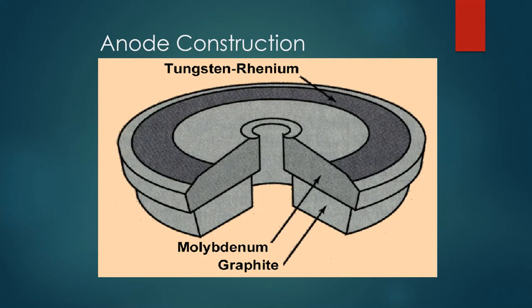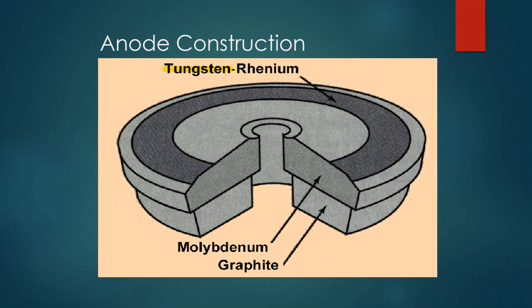The x-ray tube's anode is made of tungsten, which has a high enough atomic number to efficiently create x-rays. Usually the tungsten is alloyed with rhenium. All target interactions occur in the outer layers of the target, so the lower layers can be made of cheaper, softer metals like molybdenum and backed with graphite.